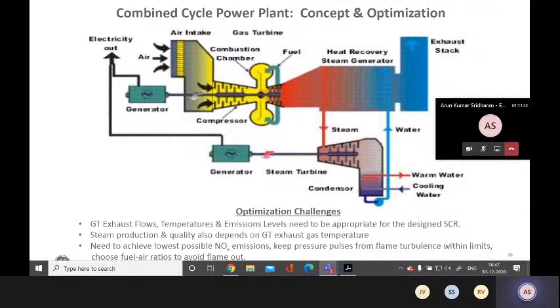So to optimize these combined cycle power plants, you really need to know the gas turbine exhaust flows, temperatures, and emission levels very well so you can design and optimize the SCR properly. You also want to know the exhaust temperature well, since the steam production and quality depend on it.